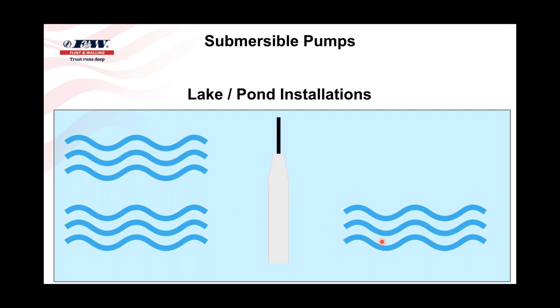They utilized a piece of plastic pipe and they would slice the end of it so they could fold it all together and clamp it up here at the top. The point is this. The only way that water could get into the suction screen of that pump is it would have to come through the bottom of that pipe.